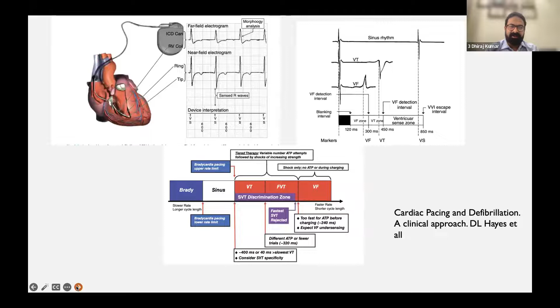So you can program 3 zones, you can program 2 zones, however you program. And there is a threshold below which the device starts pacing, whether it is 40 beats per minute or 50 beats per minute, that is the bradycardia. So you have a bradycardia zone, you have a sinus zone, you can have a VT zone, you can have a fast VT zone, and you can have a VF zone. Why do we have different zones? Because your aggressiveness of therapy would depend upon the kind of zone. Fast VT is more likely to cause syncope than a VT. So you need to be a little more aggressive than in a VT zone in a fast VT zone. And VF, you need to be very aggressive because it can cause syncope very quickly. So that's why we have these zones, and that is how the device interprets any electrical activity in the ventricle and times any electrical activity.